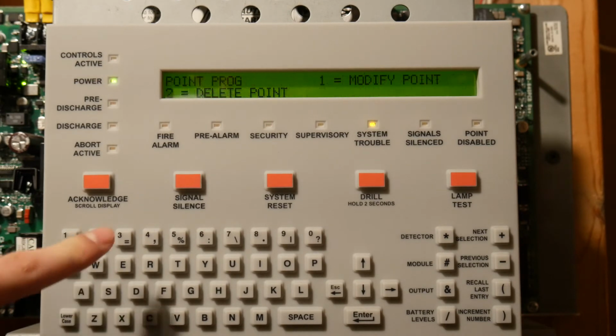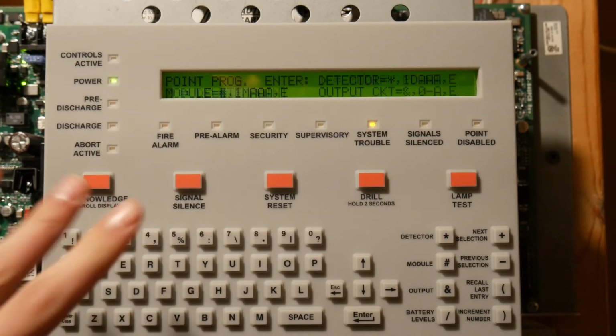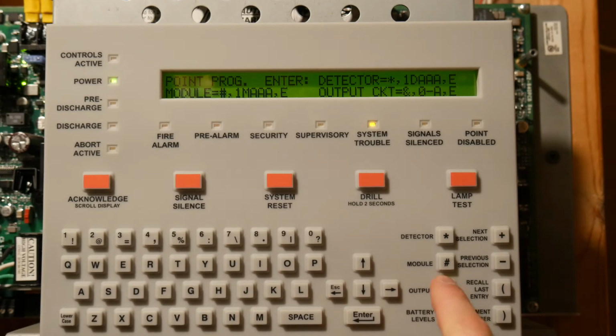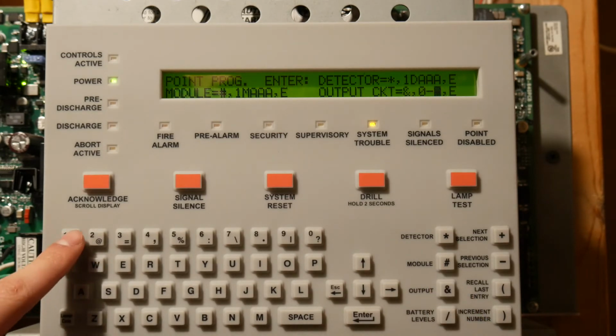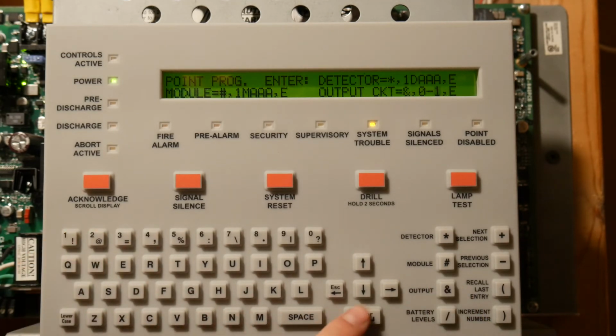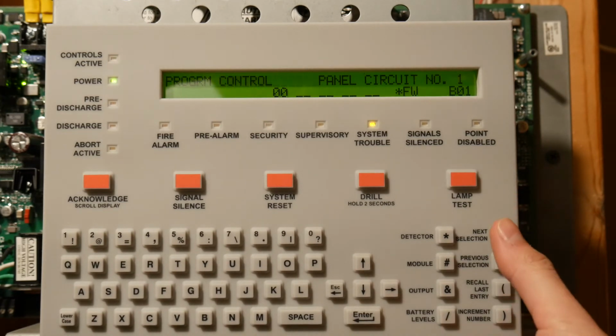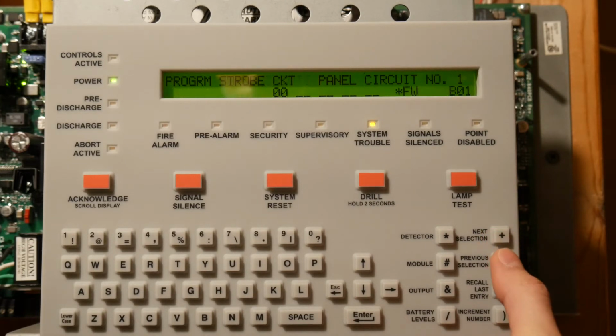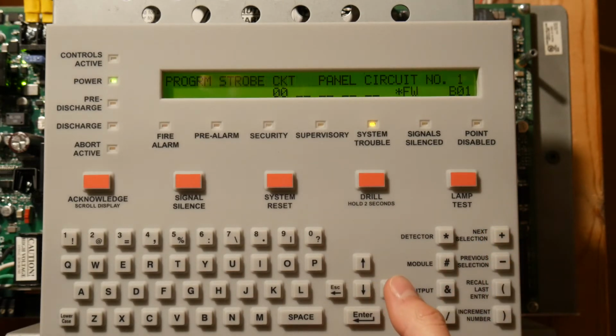So we're going to go into point, modify point. Our NACs are under point options. So we're going to press 1, because NAC 1 is where I have my system sensor alarms. So we're going to have this set as a strobe circuit. If I remember correctly, I have to set this as a strobe circuit. Yes, we set that as a strobe circuit.